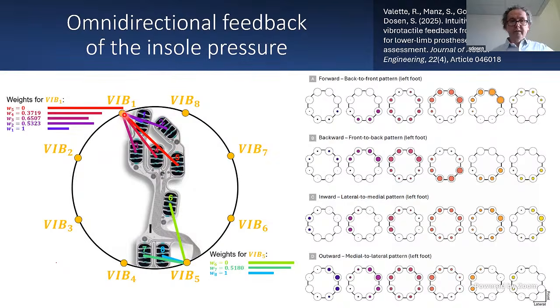Then we associate for each vibromotor the sensors from the sensorized insole with some weights. And the weight is proportional to the distance between the motor and the sensor. So each vibromotor is actually a weighted average of the signals from the sensors. The closer the sensor, the more it projects onto that vibromotor. So essentially what we get with this is that the closer the center of pressure on the foot sole is to the vibromotor, the stronger the vibromotor vibrates. And this provides information on the center of pressure in all the directions. So that's why we say it's an omnidirectional feedback.